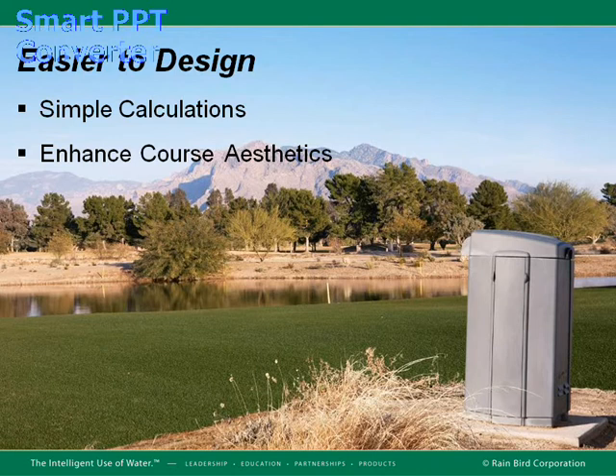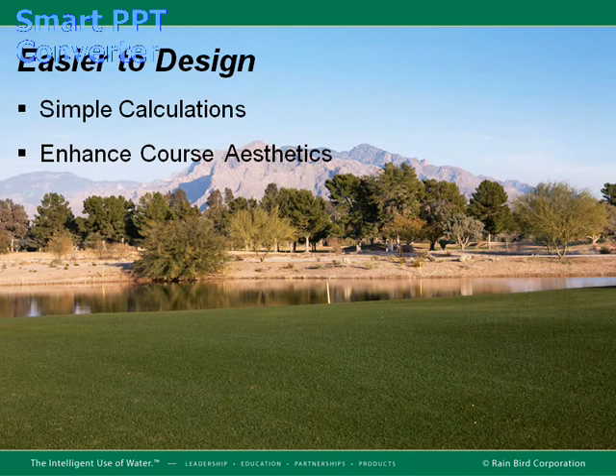With over 24 systems shipped to date in the U.S. since the IC System's release in the summer of '09, it is easy to see why irrigation consultants and designers are quickly getting on board. The system is just plain simple. Most systems require one size wire, typically 14 gauge maxi. We can put 750 sprinklers per maxi cable, and we can control 3,000 sprinklers per IC interface. No ugly controllers, individual head control, diagnostics without having to leave your office. Simple.